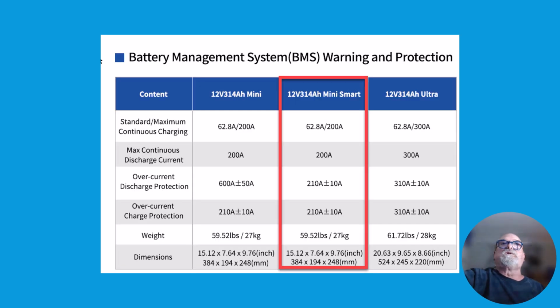So let's take a look at the BMS warnings and protections. Standard charging current and maximum charging current. What's the difference between the two? I can charge this battery at 200 amps, it says so. No, that's your maximum, and that's only for a very brief time. The reason is, remember when we talked about the BMS and passive balancing, and those resistors needing to burn off current? At 200 amps, they can't burn off enough current as heat to let the other cells catch up, and you'll have a shutoff at a low voltage and a high charging current, which will lead to a bad voltage spike.